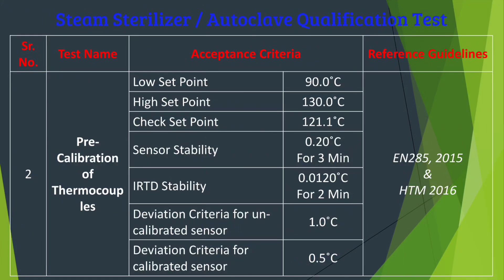Before starting performance qualification temperature mapping studies in a steam sterilizer, we need to calibrate the thermocouples being used to map the temperature. Pre-calibration is carried out at different set points: low set point at 90°C, high set point at 130°C, and check set point at 121.1°C. Sensor stability for pre-calibration is 0.2°C for three minutes, and IRTD stability is 0.012°C for two minutes.